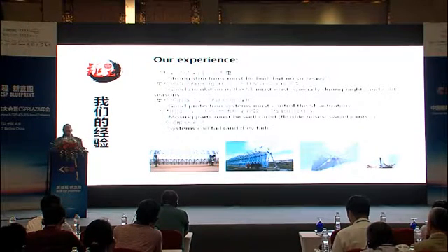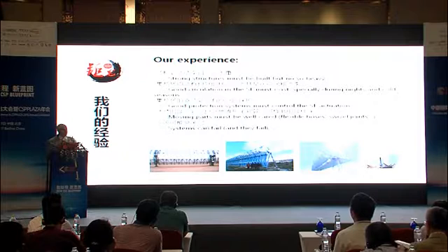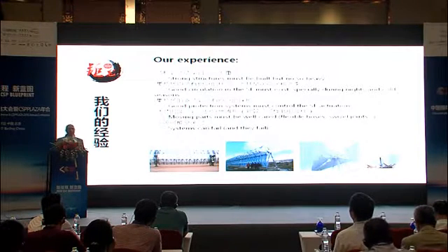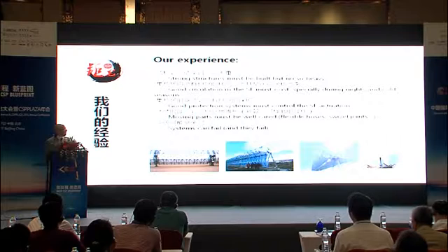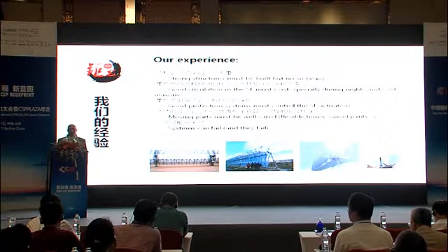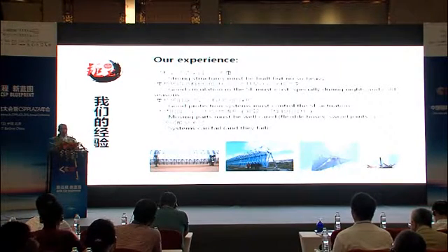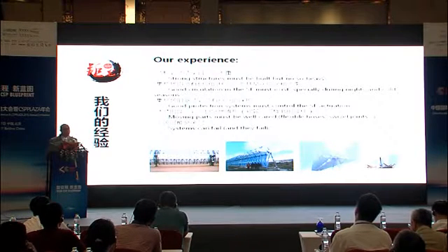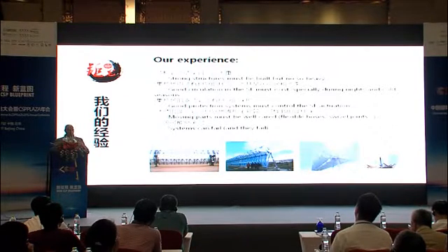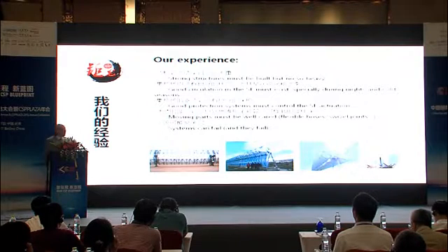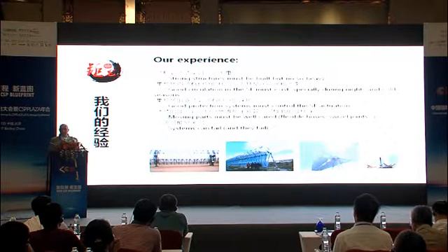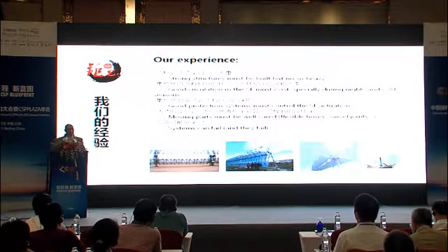The problems start exactly at this point, and continue into the second phase, which is the commissioning. The commissioning will shape the future life of your plant. If you do a good commissioning, you will enjoy a good plant for the 30 or 35 years it was initially designed for. Otherwise, if you erect a low-cost plant and do a bad commissioning, you will suffer a lot with the operation and maintenance.